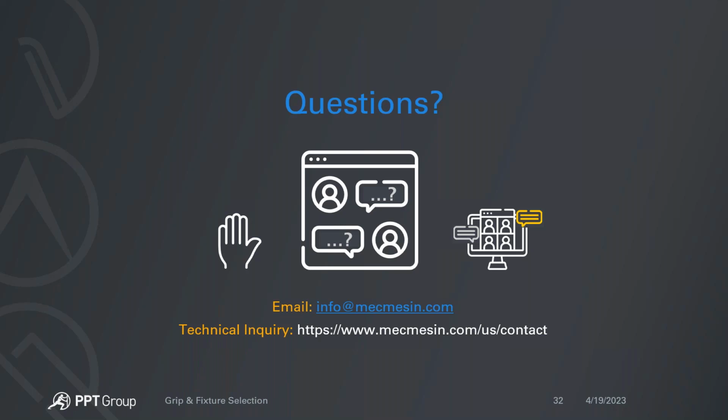Yes and no, only because crimpers are as varied as the industries or the different organizations you find them in. However, there is a guide, either a mil spec or a UL spec, that specifies, whether it's ferrule type or typical crimp connector type, the size of the cable and what the expected minimum force values should be. So I do have that data. If you have the sizes of the samples you're testing, we can run them through that data to say, hey, on this 14 gauge ferrule type connector, we should be looking at a minimum threshold of 100 pounds. If you apply at a known rate of speed and the connector comes off before it hits that minimum of 100, then it was a bad crimp to begin with.